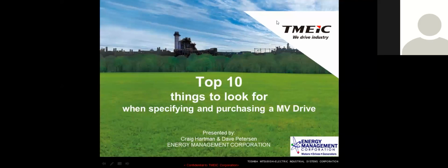Now, when you specify a low voltage drive, unless you're getting something special, most low voltage drives are pretty similar. They work in a similar way. They have the same topology and so on. Medium voltage drives, not so much. Even though you would think the only difference between a medium voltage drive and a low voltage drive is the voltage, that's not at all true. In fact, they are almost like a transformer and a panel board. Just almost like completely different products. That, of course, maybe is a little overstated.